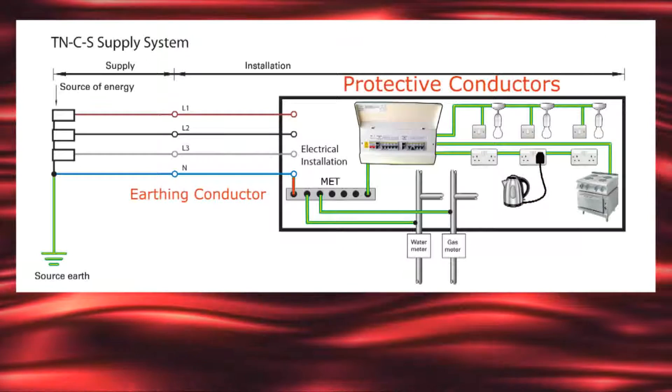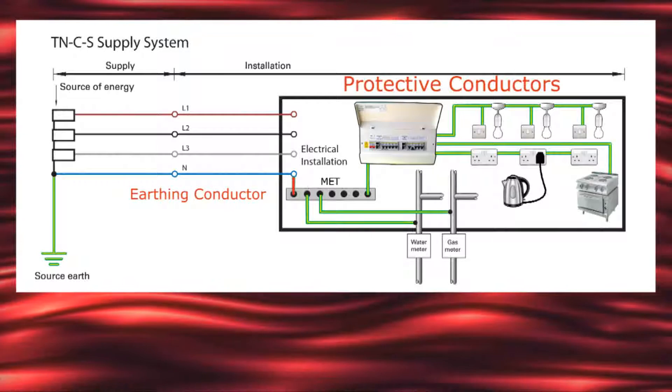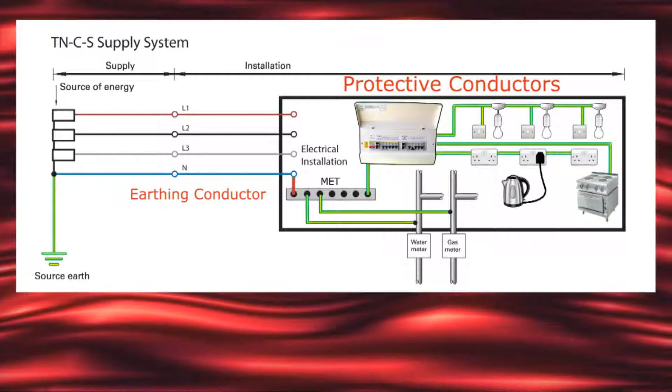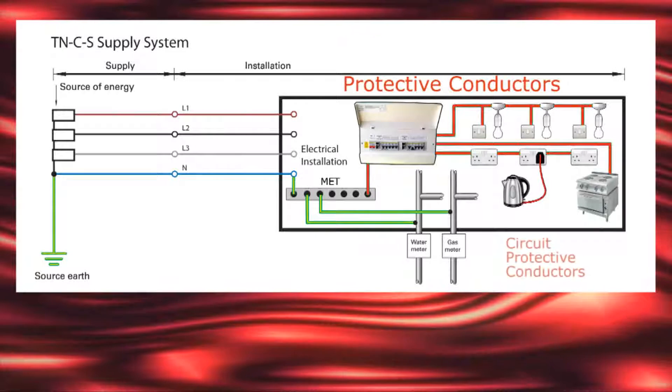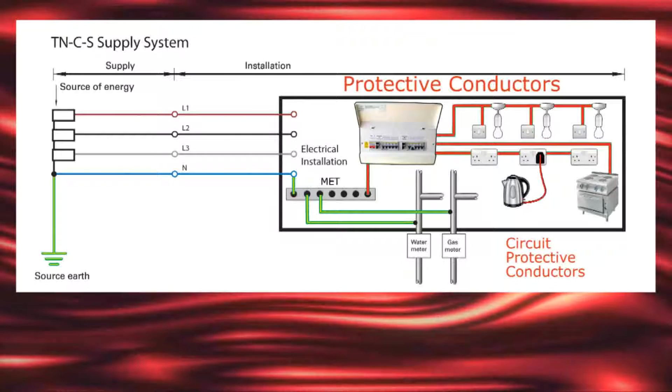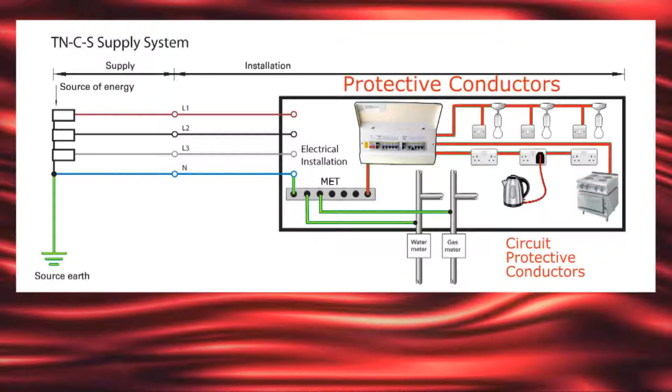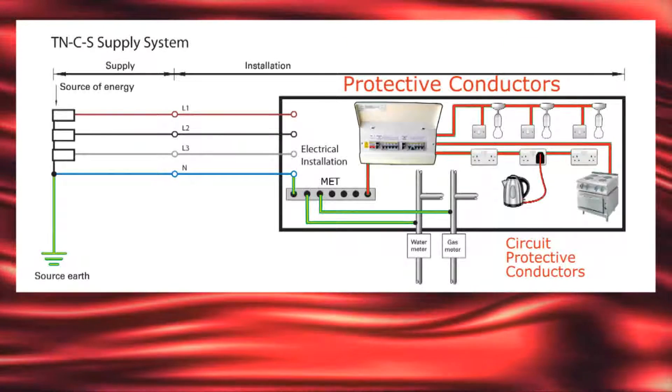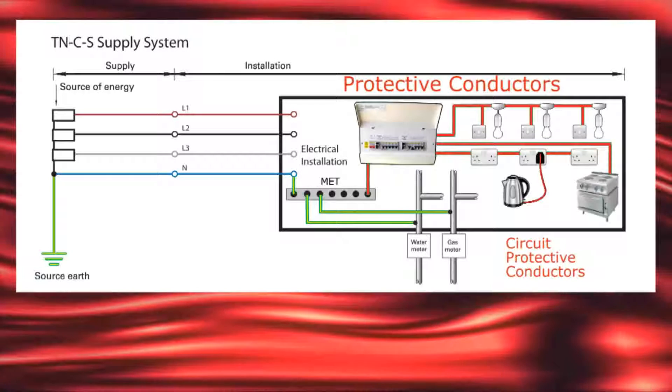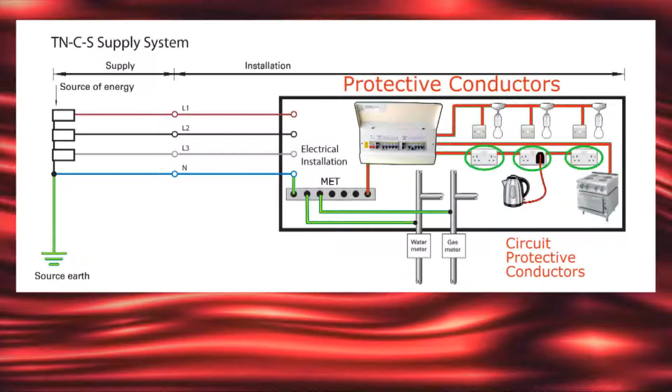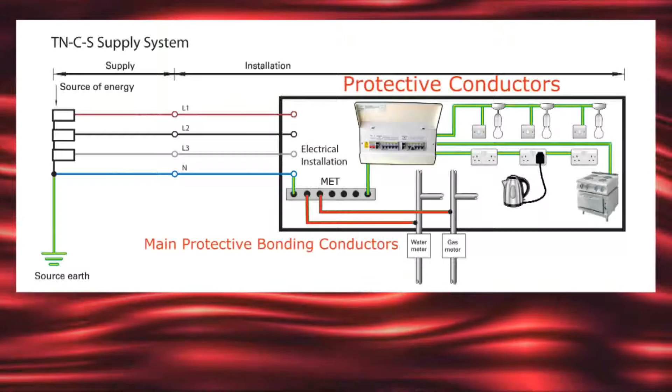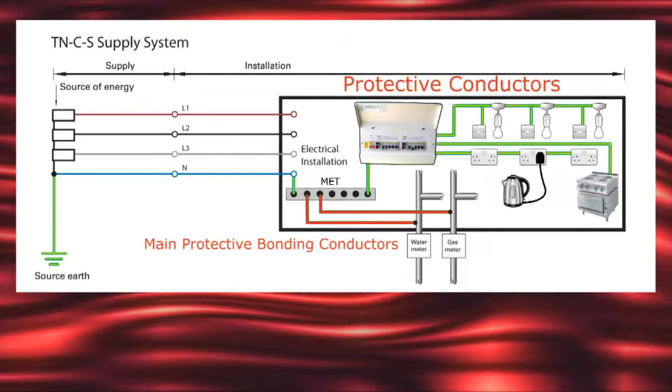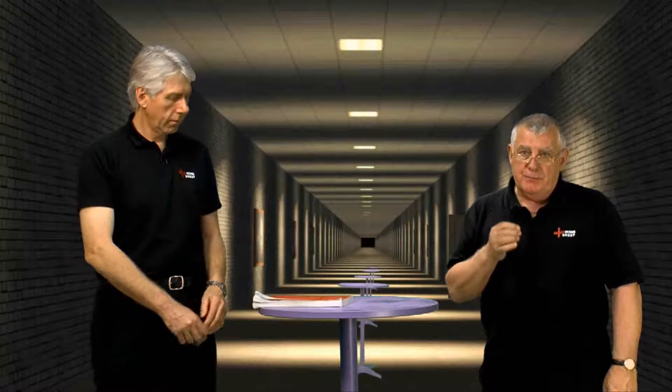There's an earthing conductor which connects between the incoming supply earth, which could be an earth electrode on a TT system, and the main earthing terminal or MET. All exposed conductive parts in the installation are connected to the MET using circuit protective conductors, CPCs. It's a requirement for CPCs to be run to and terminated at each point and accessory such as switches, ceiling roses, and socket outlets. Main protective bonding conductors connect extraneous conductive parts such as gas and water pipes to the main earthing terminal.